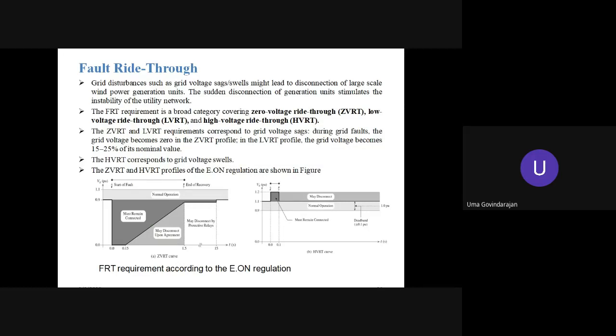This is about zero voltage and low voltage. This is the duration. Even if the grid voltage falls to 0.8, if it recovers within these 1.5 seconds, the generator will stay connected, and there is no problem of reconnection. But if the durations are exceeded, there is a possibility that the generators may pull out of the grid. This is about ZVRT and LVRT. Now HVRT, when there is a high voltage.